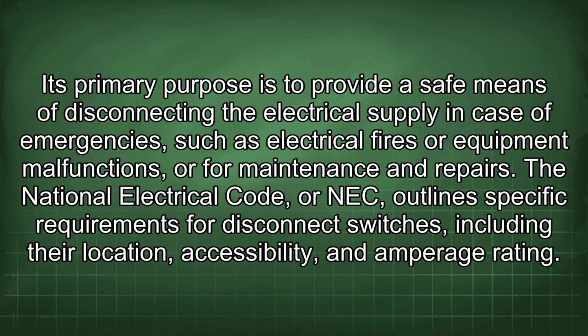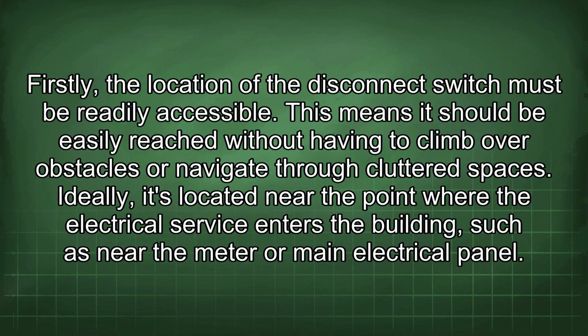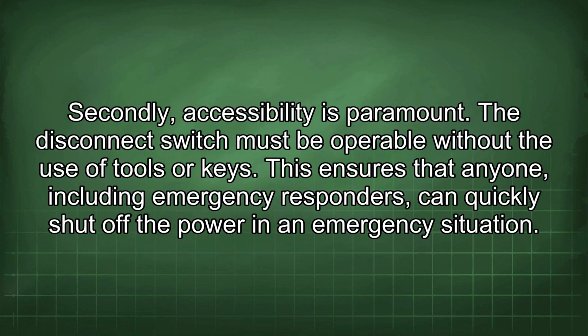The National Electrical Code, or NEC, outlines specific requirements for disconnect switches, including their location, accessibility, and amperage rating. Firstly, the location of the disconnect switch must be readily accessible. This means it should be easily reached without having to climb over obstacles or navigate through cluttered spaces. Ideally, it's located near the point where the electrical service enters the building, such as near the meter or main electrical panel. Secondly, accessibility is paramount. The disconnect switch must be operable without the use of tools or keys. This ensures that anyone, including emergency responders, can quickly shut off the power in an emergency situation.